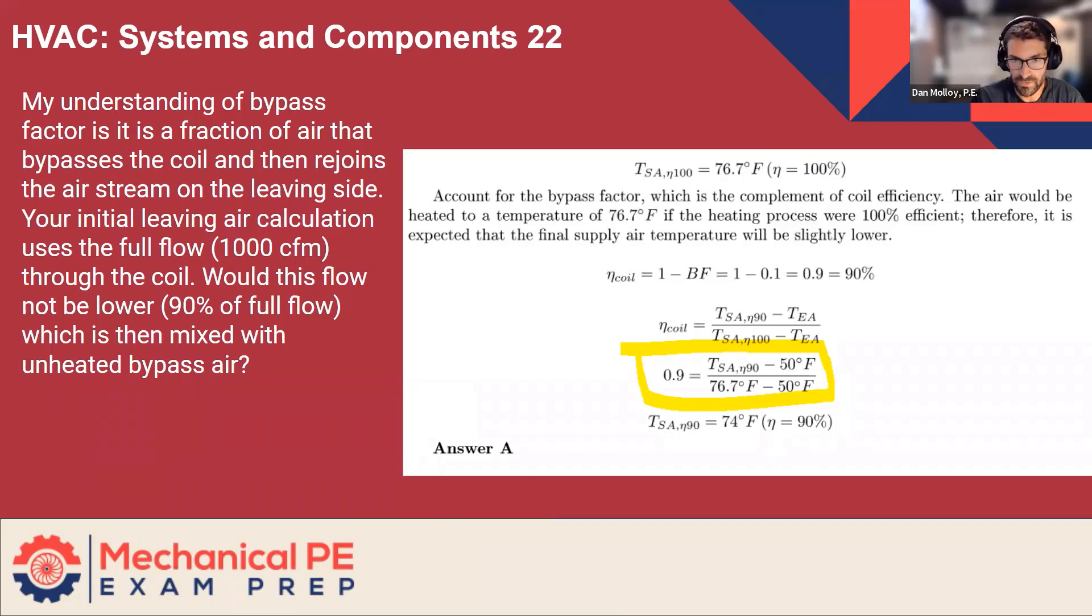Your initial leaving air calculation uses the full flow, 1000 CFM, through the coil. Would this flow not be lower, 90% of full flow, which is then mixed with the unheated bypass air?